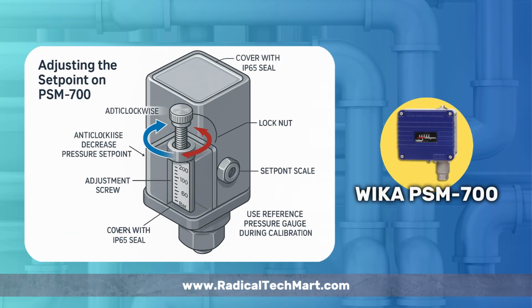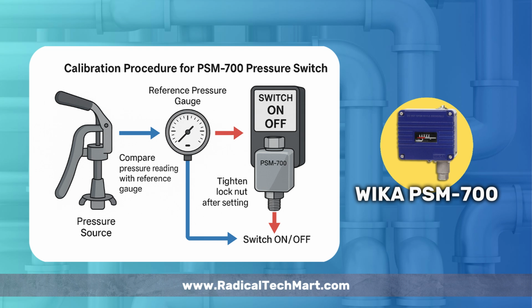The PSM-700 features a front-mounted adjustment screw and a visible pressure scale for easy setpoint calibration. To adjust, rotate the screw clockwise to increase the cutout pressure and anticlockwise to reduce it. Always use a reference pressure gauge while calibrating to ensure accuracy. Once set, lock the adjustment screw and close the top cover tightly to maintain IP65 protection. This design makes field calibration fast and safe, even in harsh working conditions.